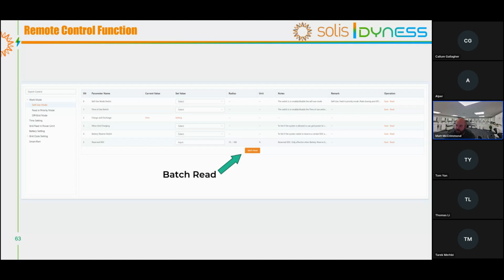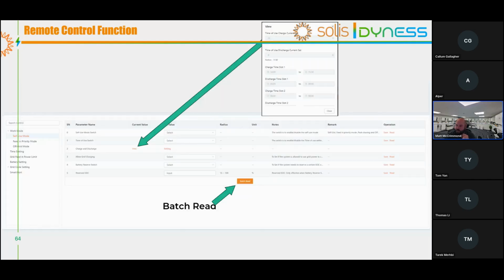So once you've got into this setting, you can then click batch read. It'll then populate what the current values are, and then you can change whatever you want. Once you've selected from the drop-down menu, you click save. If you look at, for example, the charge and discharge window, you can click view, so you can just see exactly what's set up, what time windows have been set up, what current's been set up. And if you wanted to change that, you just click on settings, and then once you do it, you click save, and then it'll send the command to the inverter. So it means that you can change the time of use remotely. You can do that through the web browser, which is what's shown here, or you can do it through our app. So our app can do that for you.